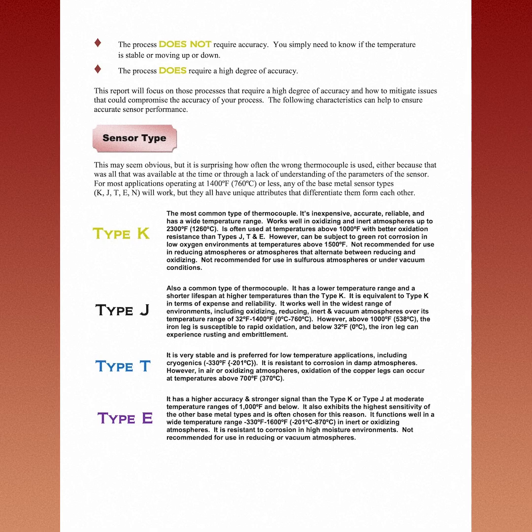Type E has a higher accuracy and stronger signal than the Type K or Type J at moderate temperature ranges of 1000 degrees Fahrenheit and below. It also exhibits the highest sensitivity of the other base metal types and is often chosen for this reason. It functions well in a wide temperature range from minus 330 to 1600 degrees Fahrenheit, or minus 201 to 870 degrees Celsius, in inert or oxidizing atmospheres. It is resistant to corrosion in high moisture environments. Not recommended for use in reducing or vacuum atmospheres.